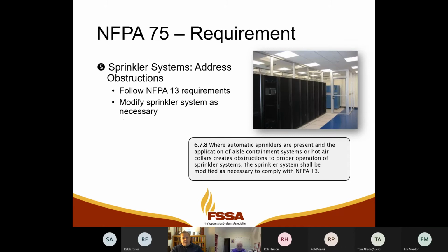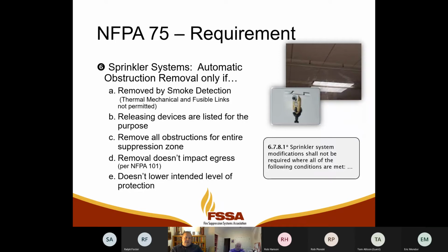Number 5, sprinkler systems, you have to address the obstructions. This should be pretty self-evident to this group. Follow NFPA 13 requirements and modify the sprinkler system as necessary for those obstructions. This is pretty detailed in the code. You have to have automatic obstruction removal. Like if you're going to use fusible links and you're going to say it's automatic obstruction removal, if that's your method and you're not going to modify the sprinkler locations and you're going to depend on the strip curtains dropping down or whatever, the obstruction being removed under fire conditions, it must have these 5 things.